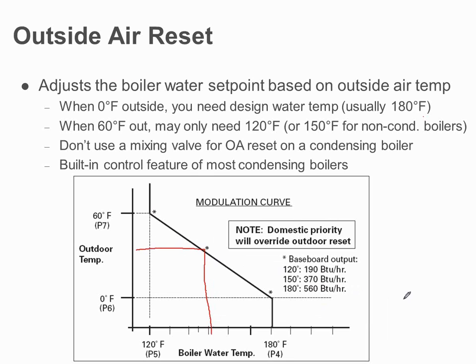So outdoor air reset, once you set up your two points per se, at 0, what's my max temperature? 180, and at 60 degrees, what's the water temperature I need? In this example, we're using 120. So anywhere in between that, now we're saying, okay, at 45 degrees, I need 130. At 10 degrees, I might need 170. All that time, you're sitting there saving energy because you're not bouncing off of that 180 like every cast iron boiler is doing in existence today. Okay, so outdoor air reset is part of all these condensing boilers because they always want to be running as low as possible. That's why most of them have these 5-to-1 turn down rates, which means you could have a 100,000 BTU condensing boiler. It could be running at 20,000 BTUs, and it could be running there all day.